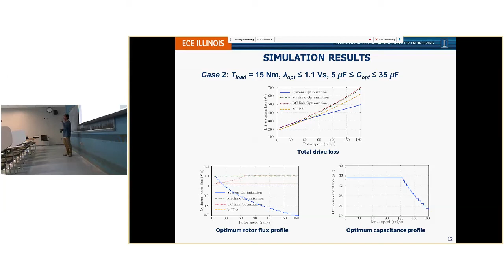It's similar to that. But there is some good news: we don't really have to dynamically vary the capacitance, because we do a sensitivity analysis of loss. What does this mean? We look at how loss is sensitive with respect to the capacitance value. 5 to 35 microfarads was our domain of interest. We see that the losses within this range, from orange to red in these curves, are very close, meaning the drive loss is not that sensitive to the capacitance value. However, beyond 35 microfarads, the losses go up tremendously. That's not a problem for us because we've restricted our domain of interest to this range. So for this machine, with this set of parameters, we will be okay with fixed capacitance, and similarly for nominal loading conditions.